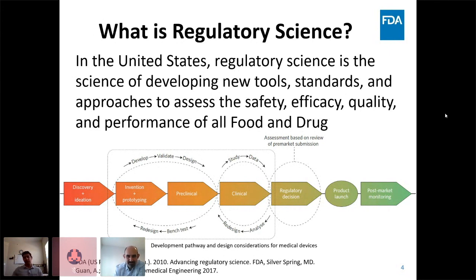So you see all these endpoints have to follow that standard, and you cannot just do them in your basic laboratory like you have in school. It should be done in a GLP environment. GLP means good laboratory practice. So if you do the testing in your own lab and send it to FDA, FDA doesn't accept it. Not all testing has to be GLP, but specific testing, usually related to safety, such as animal study and biocompatibility, should be done under GLP.